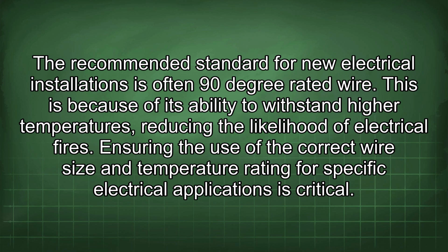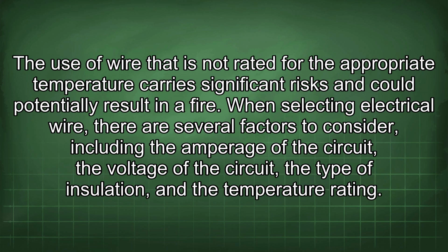Ensuring the use of the correct wire size and temperature rating for specific electrical applications is critical. The use of wire that is not rated for the appropriate temperature carries significant risks and could potentially result in a fire. When selecting electrical wire, there are several factors to consider, including the amperage of the circuit, the voltage of the circuit, the type of insulation, and the temperature rating.